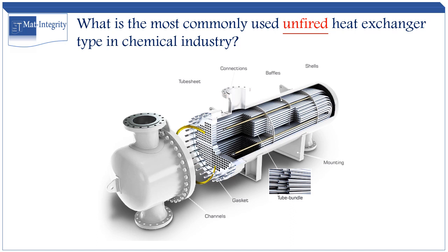The tube bundle also contains baffles. These baffles are thin but stiff plates installed to maintain distances between tubes and direct the shell fluid flow. The tube bundle assembly is usually inserted inside the shell until the tube sheet connects with the flanged end of the shell.